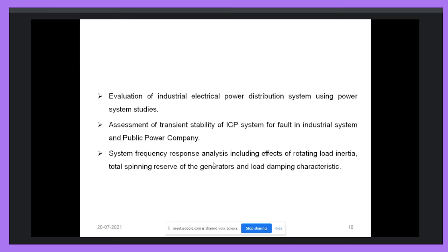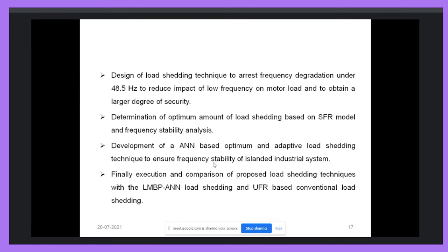And for the load shedding design, system frequency response analysis is important. We have to set the frequency limits to design load shedding techniques. We have to determine the optimum amount of load shedding based on the system frequency response and frequency stability analysis. We have to develop ANN based optimum and adaptive load shedding techniques for the stability of the islanded system.